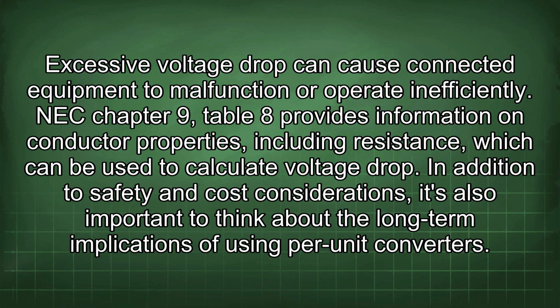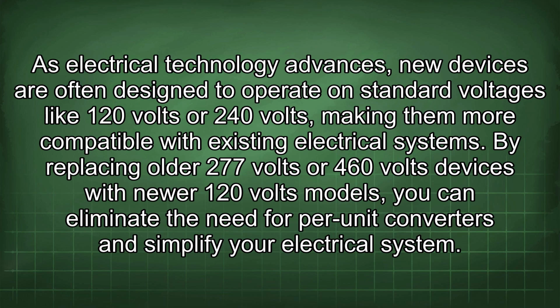In addition to safety and cost considerations, it's also important to think about the long-term implications of using per unit converters. As electrical technology advances, new devices are often designed to operate on standard voltages like 120 volts or 240 volts, making them more compatible with existing electrical systems. By replacing older 277 volts or 460 volts devices with newer 120 volts models, you can eliminate the need for per unit converters and simplify your electrical system.